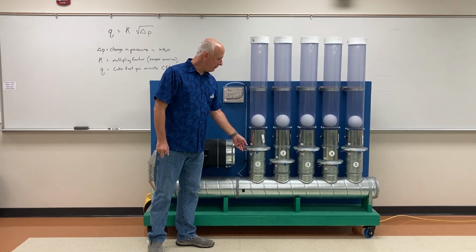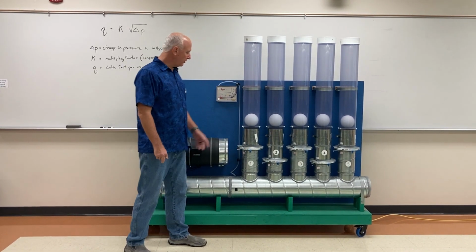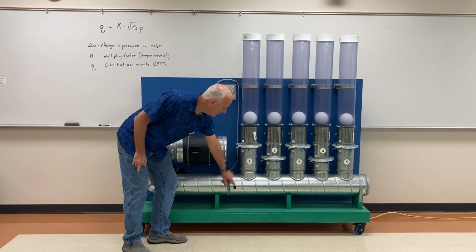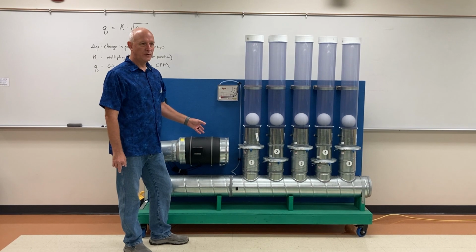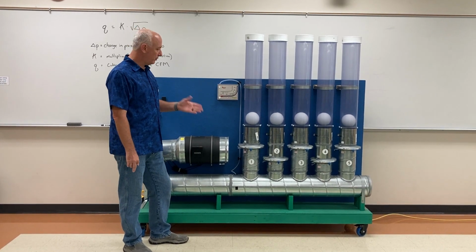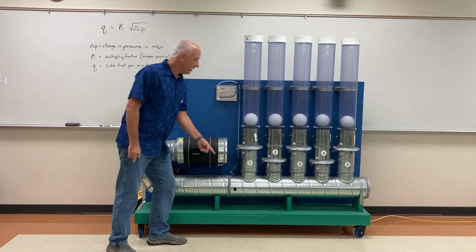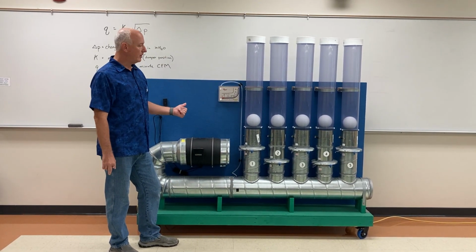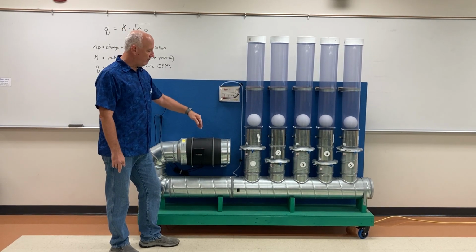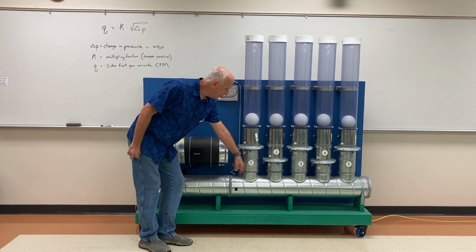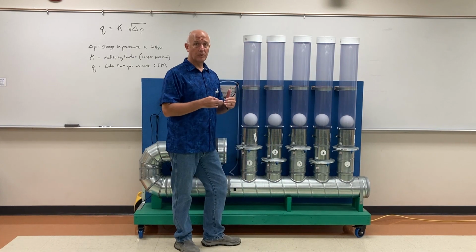With this system, we've done the pressure reading and done the math on this. I've also included an additional port where we can actually do a duct traverse, and using the tools to read this, the same meter and a pitot tube, we can actually take the airflows, run it through a couple of different calculations, and we can verify how much air is actually passing this point compared to our readings of each of these, and they should be equal.